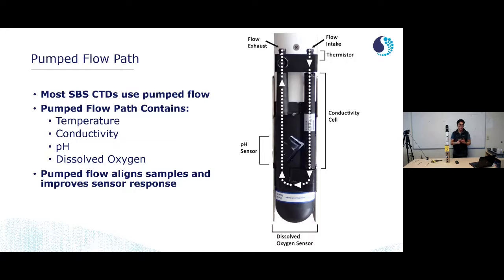Because your pH sensor, your temperature sensor, your dissolved oxygen sensor, and your conductivity sensor are all plumbed together, you know that they're all sampling the same water. You know that when your instrument is sampling, it is actually pulling in a new sample of water. You don't have to rely on natural flushing or hope that currents are going to replace the water. You can guarantee that the pump is going to pull in a new sample for your HydroCAT. And so, as I mentioned, temperature, conductivity, pH, and dissolved oxygen are all contained within this pumped flow path, and that's aligning your samples, improving sensor response.